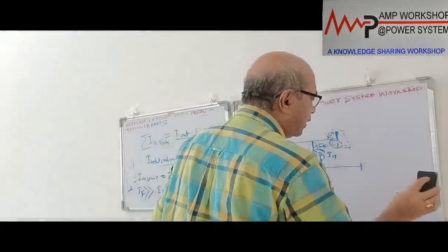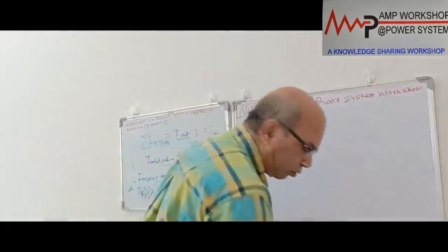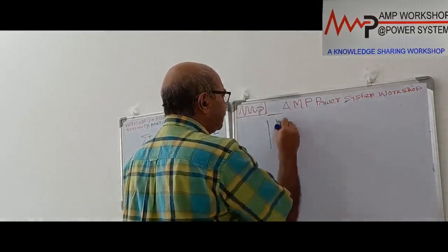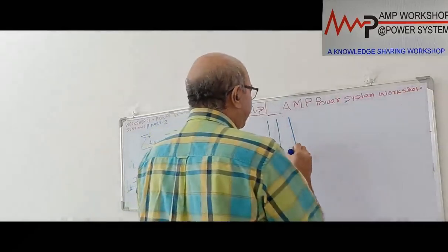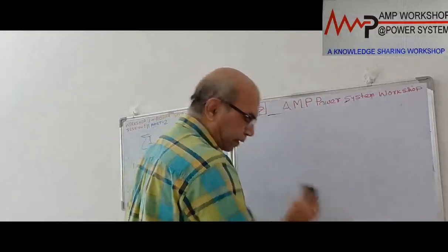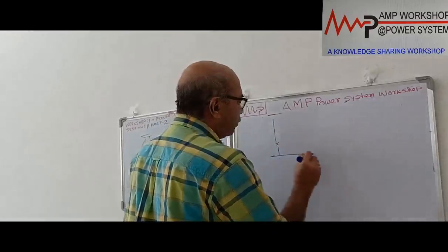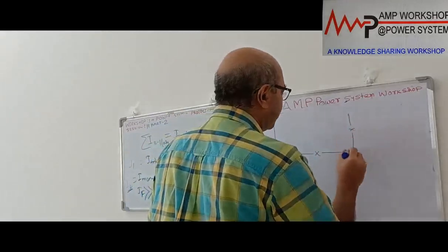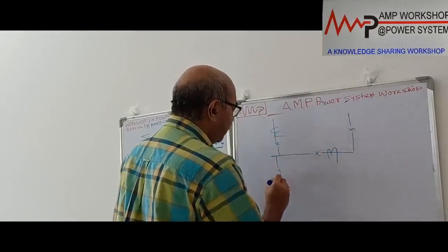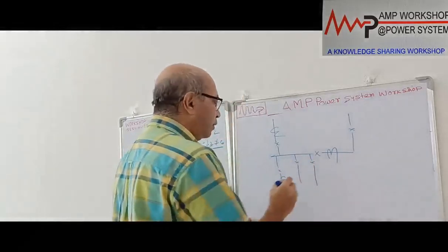So if we do a multiple incoming and outgoing current differential scheme, how does it look? I am just drawing one CT wiring diagram, a 3-phase wiring diagram. Suppose we are not considering too many feeders. First we draw the single line diagram, then it will be clearer. So this is an incomer, this goes to the bus coupler, and this is another incomer. We have a CT over here, a CT over here, and then we have an outgoing feeder with a CT. Suppose I am putting one or two outgoing feeders.